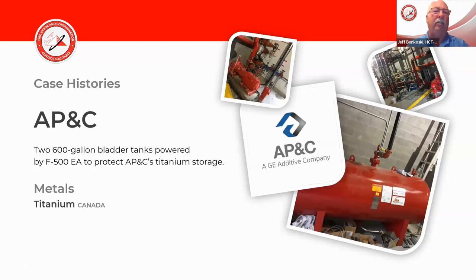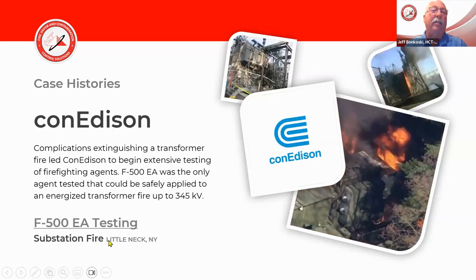And just some case histories. So here's one that's showing two 600-gallon bladder tanks that have the F500 used for titanium storage, that class D metal, where we don't want water, but yet we want to have some type of fire protection to protect our facility, protect our employees. Well, the solution was F500. So we've got systems. Con Edison using it for protecting transformers or being able to extinguish transformers.